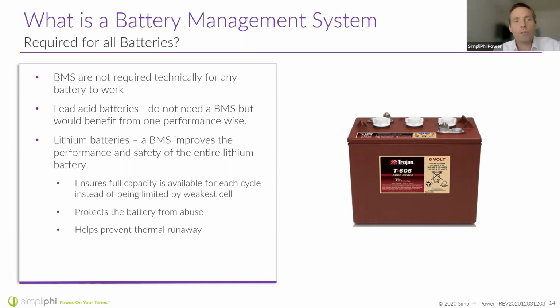Most of the health was maintained through the charging system, which was external to the battery. If you've participated in installations using deep cycle lead acid batteries, you typically programmed the charger, and the charger would try to maintain the health of the battery. You might have different cycles to try to desulfate the battery, etc. But there was no internal BMS in a lead acid battery, especially with low voltage batteries, it was less necessary.